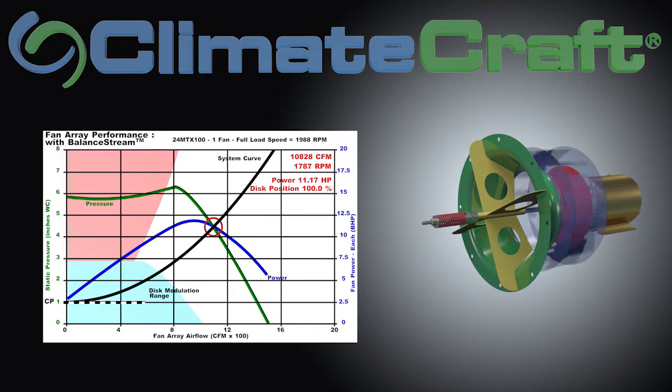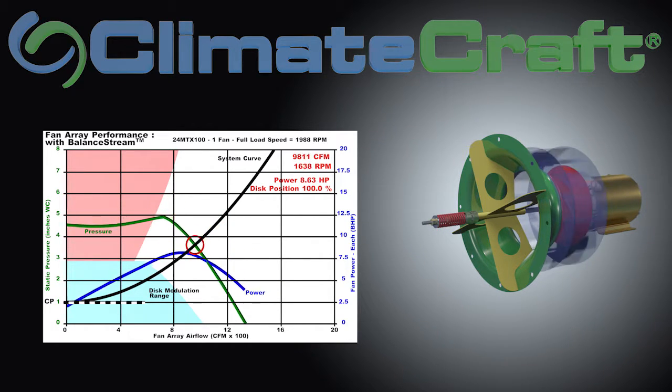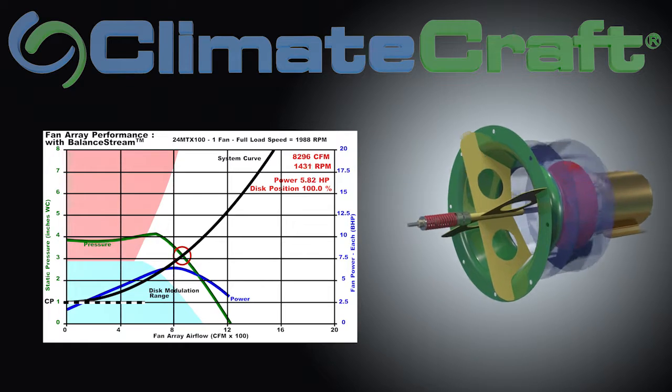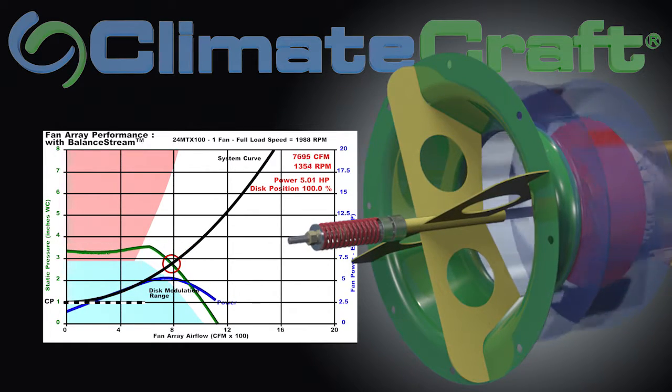As the system VAV boxes or dampers begin to close, the system requires less flow. At this point on the curve, this fan is operating the same as any other fan in an array configuration. As the system continues to unload, at about 50 percent airflow we enter the blue shaded region on the graph — this designates where BalanceStream begins to engage.